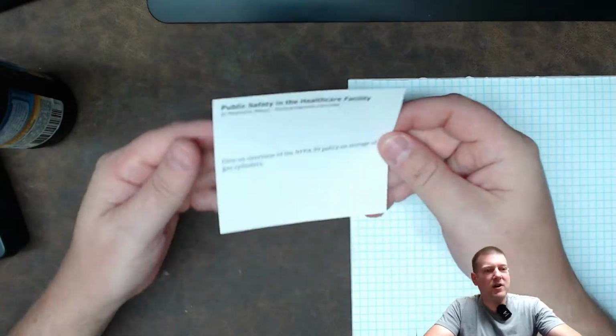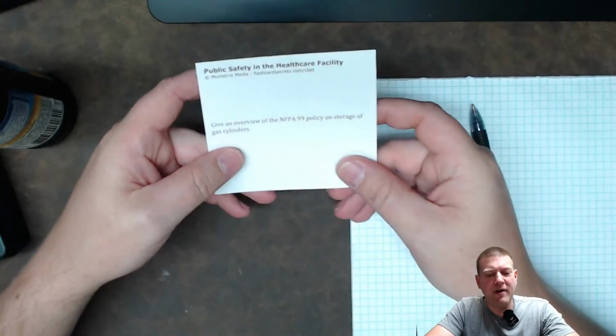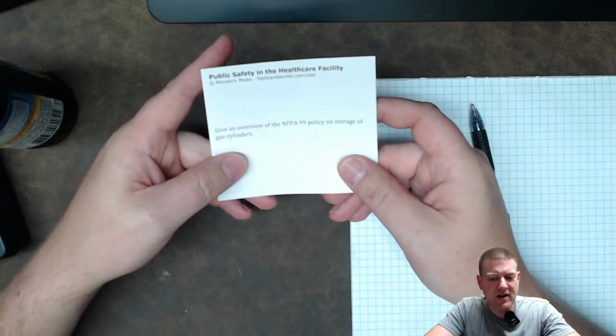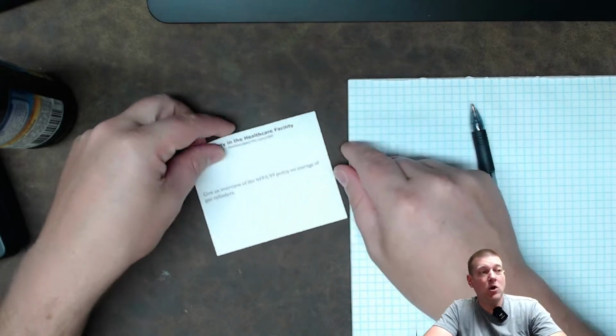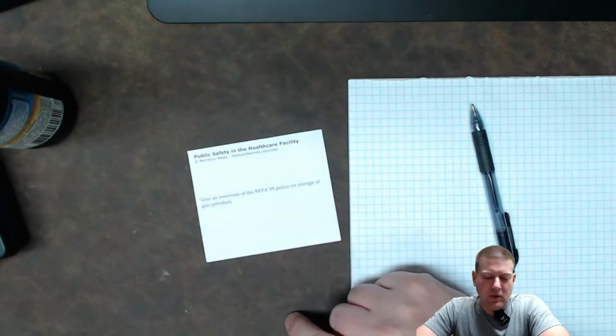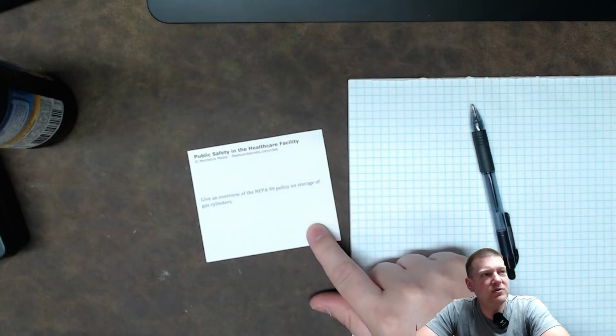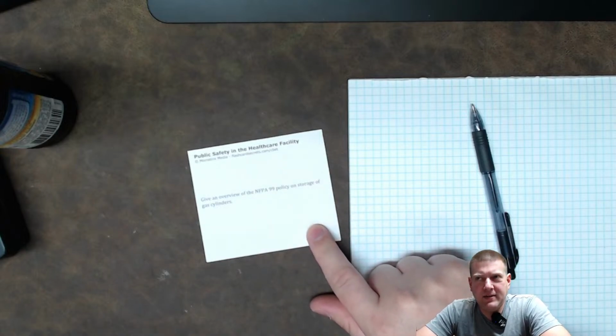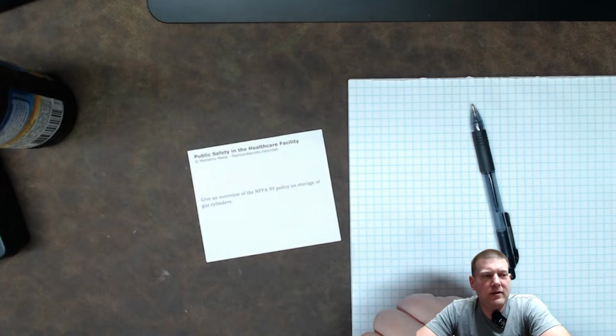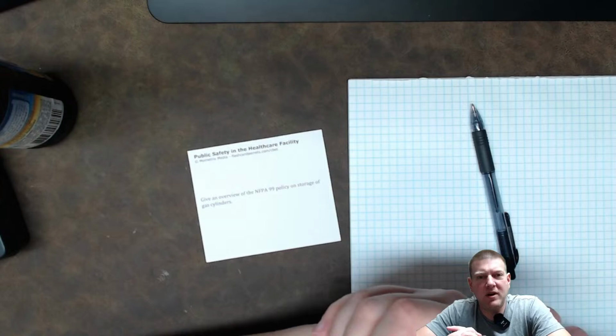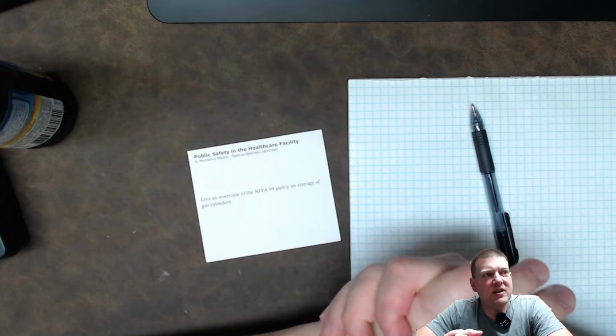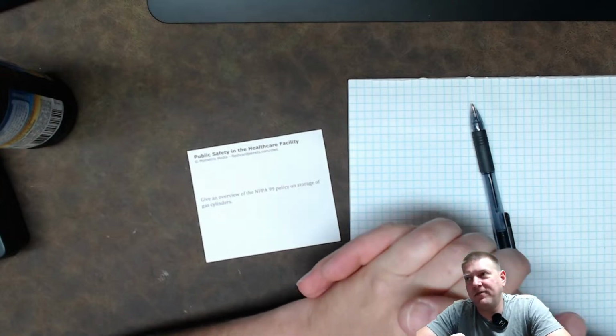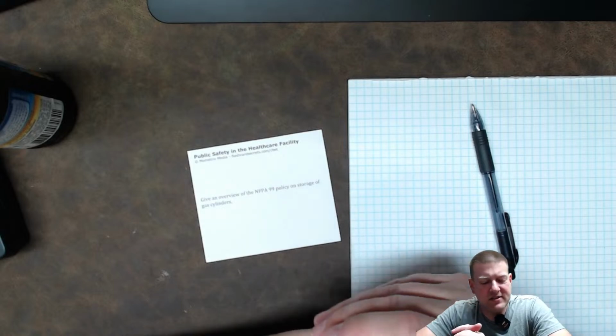So the very first card right here, it says, give an overview of the NFPA 99 policy on storage of gas cylinders. Ooh, okay. Well, this was one of the first topics we covered yesterday. And for cylinders, it basically says they are separated based on their properties. So oxidizers have to be kept separately from flammable liquids and gases.